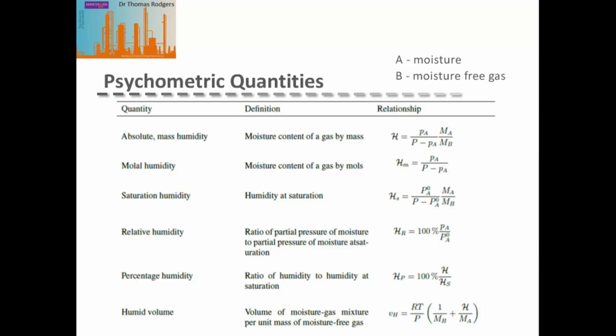The absolute humidity must be modified by the ratio of the molecular weight of the moisture to the molecular weight of the moisture-free gas to convert it into mass. It is also possible to express this as a molar humidity. The saturation humidity is defined the same as the absolute mass humidity, except that instead of using the actual vapor pressure of the moisture, we use the saturation vapor pressure.